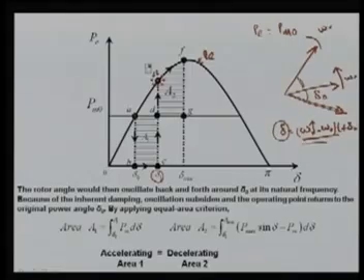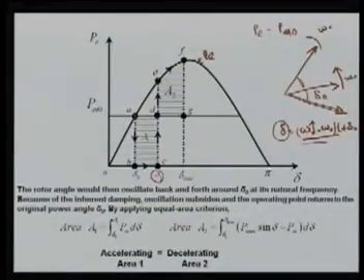You can see the electrical power is now more than your mechanical power, which means you are taking more power. So whatever energy is stored in the machine will be taken out, and this area is called decelerating. Here it was accelerating, and from here it will decelerate till F, when the oscillation will again become 0.